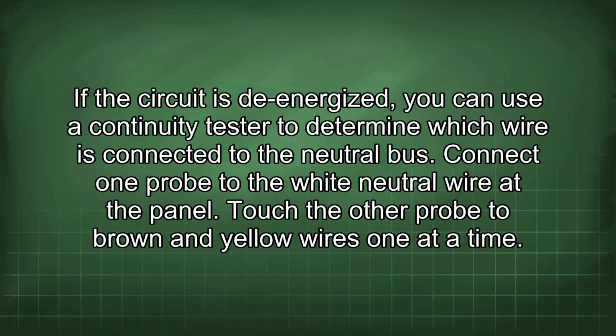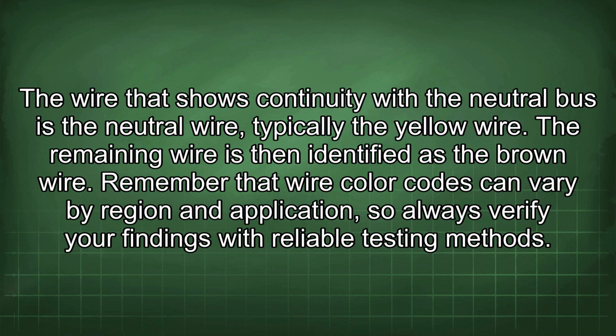If the circuit is de-energized, you can use a continuity tester to determine which wire is connected to the neutral bus. Connect one probe to the white neutral wire at the panel. Touch the other probe to brown and yellow wires one at a time. The wire that shows continuity with the neutral bus is the neutral wire, typically the yellow wire. The remaining wire is then identified as the brown wire. Remember that wire color codes can vary by region and application, so always verify your findings with reliable testing methods.